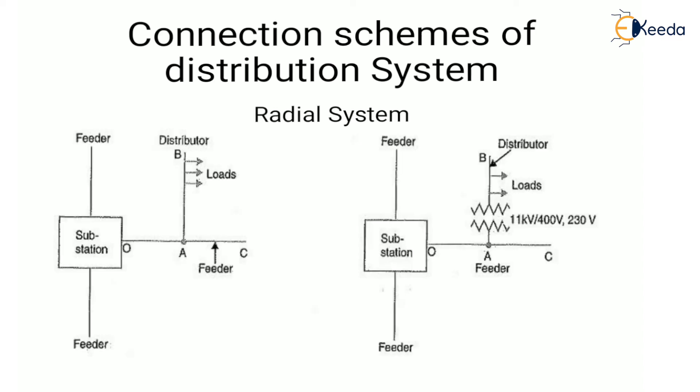Now let's look at the connection schemes of a distribution system. The first is the radial system — feeders are radiated from the substation and feed the distributor at only one end. AB is the distributor. This system is employed when power is generated at a low voltage and the substation is located at the center of the load.